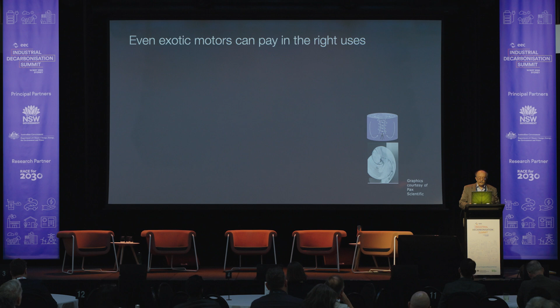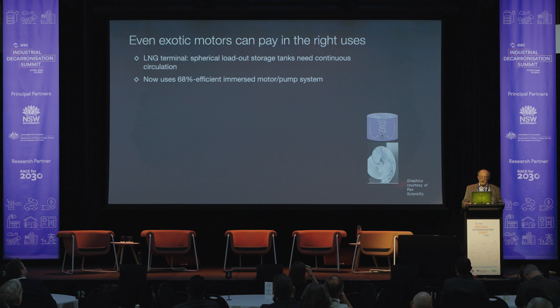So we found that the LNG was being circulated by an immersed motor pump system with a combined efficiency of 68%. But it'd be worth paying a lot for a high-temperature superconducting motor like the Navy uses that would run a good pump at a combined efficiency of 89%, reducing the product wasted by boil-off by 2/3 and leveraging all the savings back upstream to liquefy that gas.